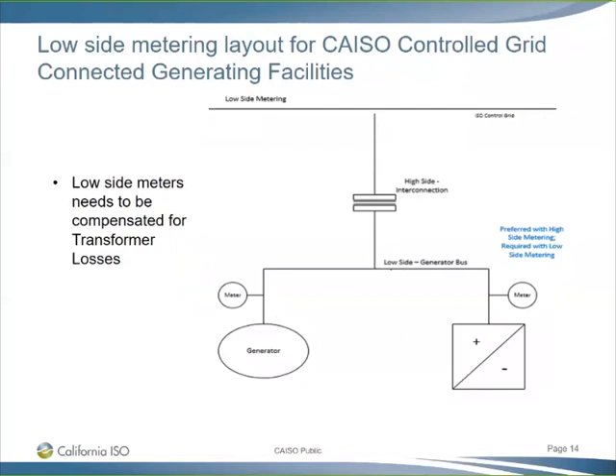That's why I said it applies for either a single resource ID or multiple resource IDs. If it's multiple resource IDs, we need one meter on each resource, so there's a meter on-site. If it's a single resource ID, they don't have to meter it separately. They can have one meter right below the transformer to measure output, and the additional meter is for RPS reporting. These diagrams mix things together, which makes it a little hard to understand. So this diagram does assume two resource IDs, but if you had just one, you could use a single meter, except for that possible RPS reporting exception, right?